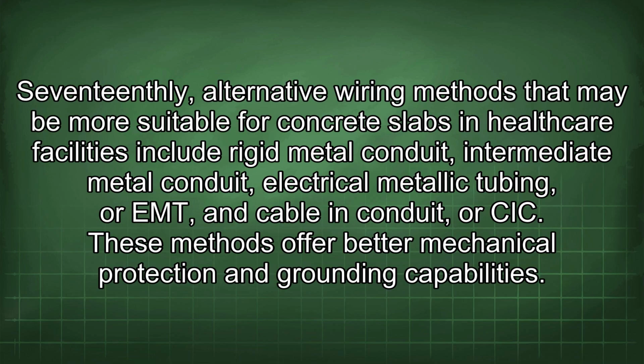17thly, alternative wiring methods that may be more suitable for concrete slabs in healthcare facilities include rigid metal conduit, intermediate metal conduit, electrical metallic tubing, or EMT, and cable in conduit or CIC. These methods offer better mechanical protection and grounding capabilities.